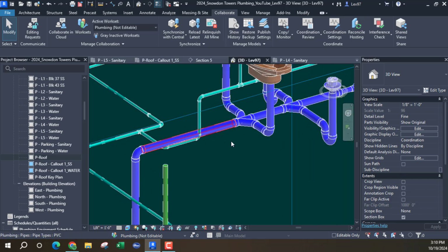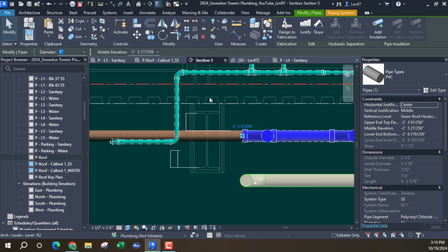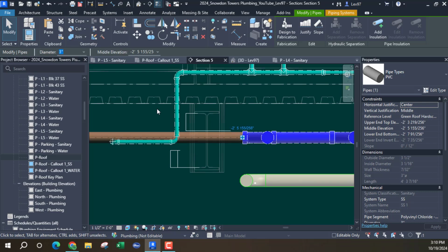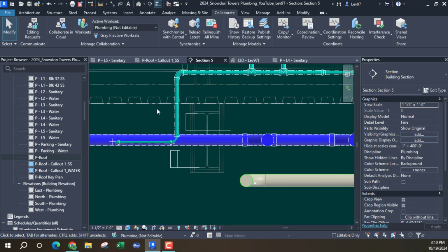Okay, so I'm going to come down just because what I would not do is put one of my pipes up in this area, right on in here. That I would change, okay? But I'm not changing. I hope things are going to fall, okay? So you want to be in that middle third. So now we're in the middle third of the beam. So everything looks to be okay.